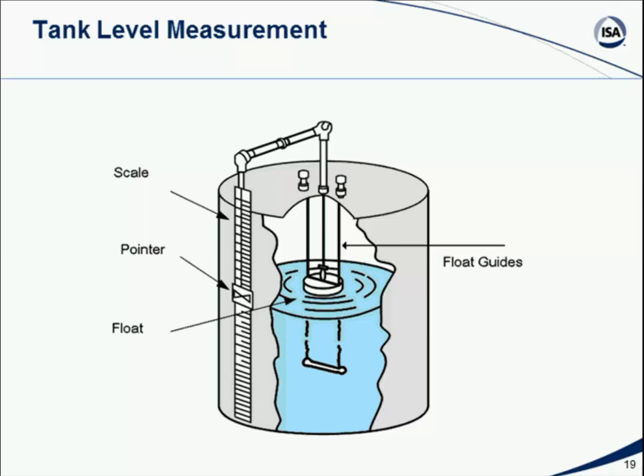Of course, the thing you've got to keep in mind is that it's an inverse measurement. As the level goes up, the pointer goes down. So the pointer at the bottom of the tank indicates a full tank. The pointer at the top of the tank indicates an empty tank.